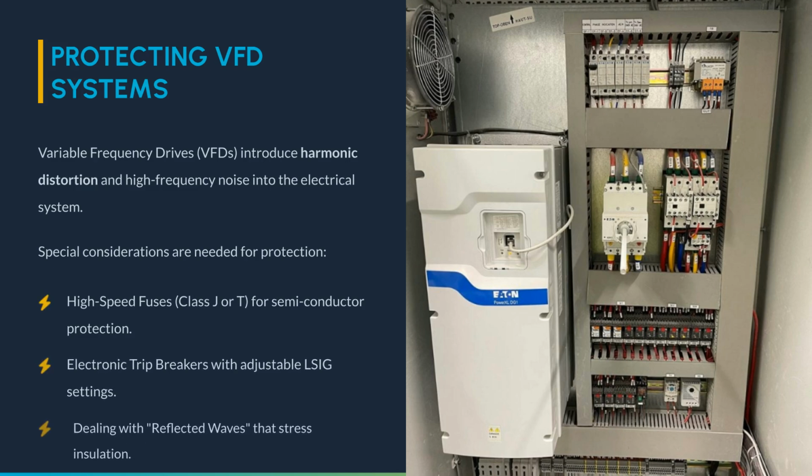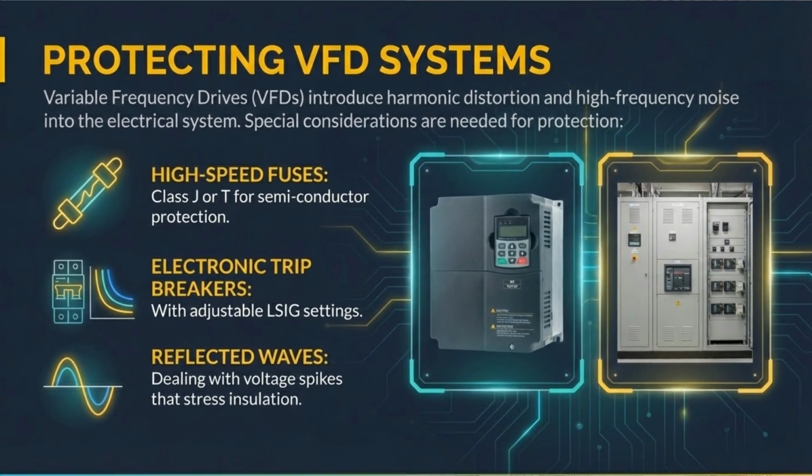the facility. Protecting variable frequency drive, or VFD, systems requires special attention, as they introduce harmonic distortion and high-frequency noise. Proper protection involves using high-speed fuses, electronic trip breakers with adjustable settings, and addressing reflected waves that can damage motor insulation.